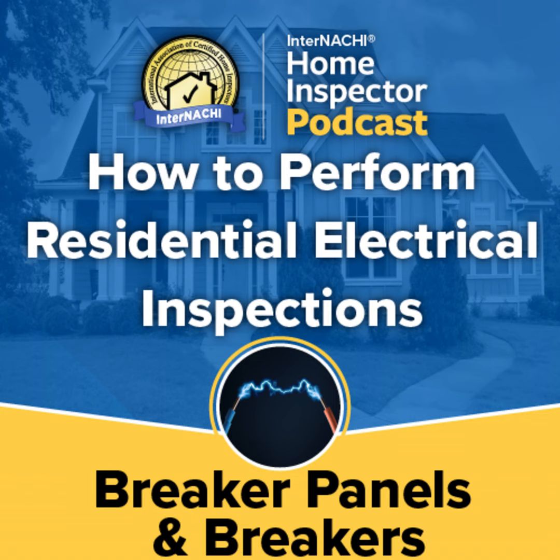Circuit breakers fall into 4 categories. 1. 240-volt double breakers. 2. 120-volt single breakers. 3. GFCI breakers. 4. AFCI breakers. All of these require some specialized knowledge to properly evaluate. Remember, we are talking about energized components. Safety is paramount when investigating electrical panels and overcurrent protection devices.